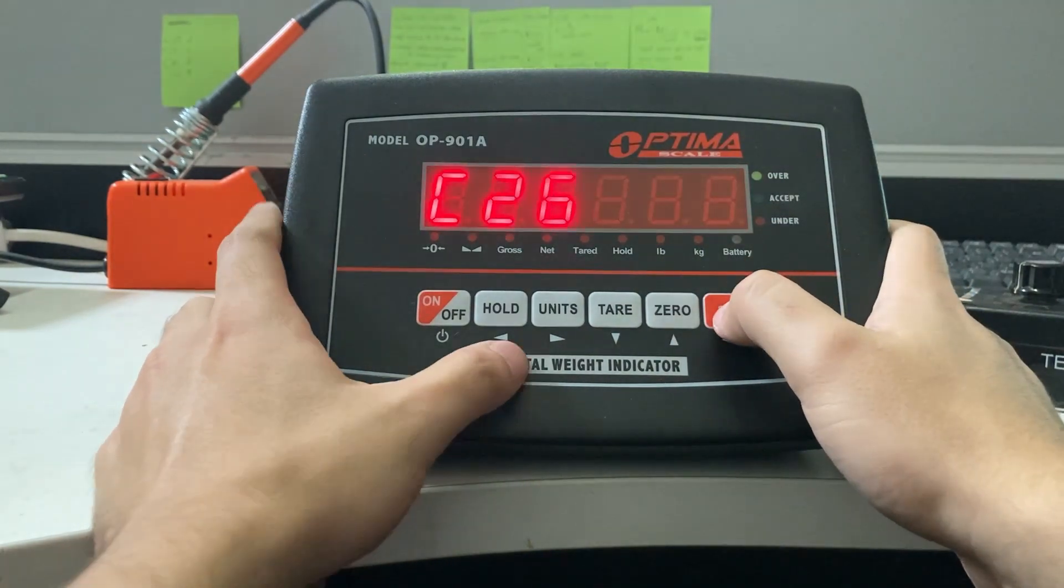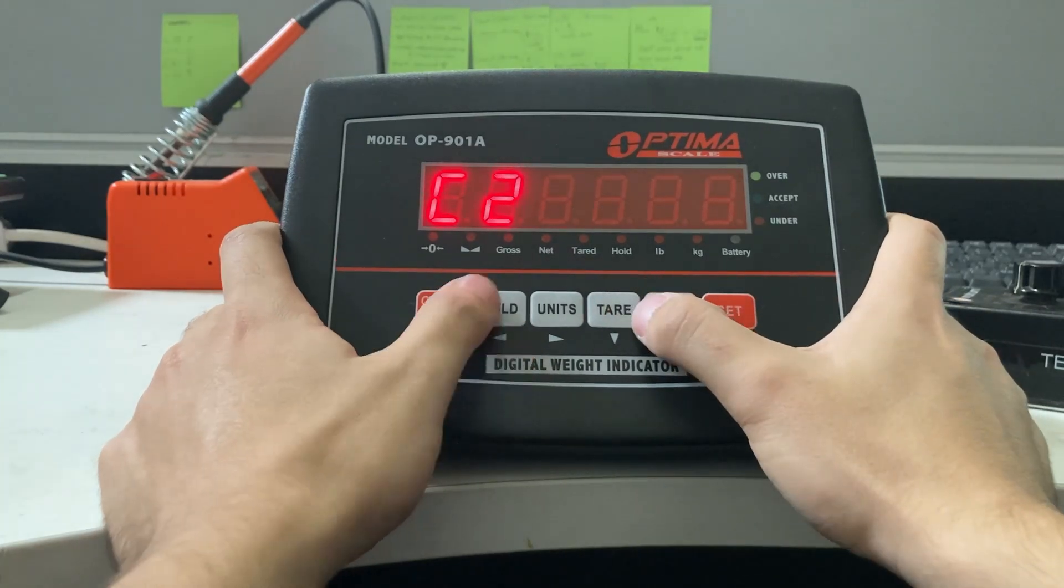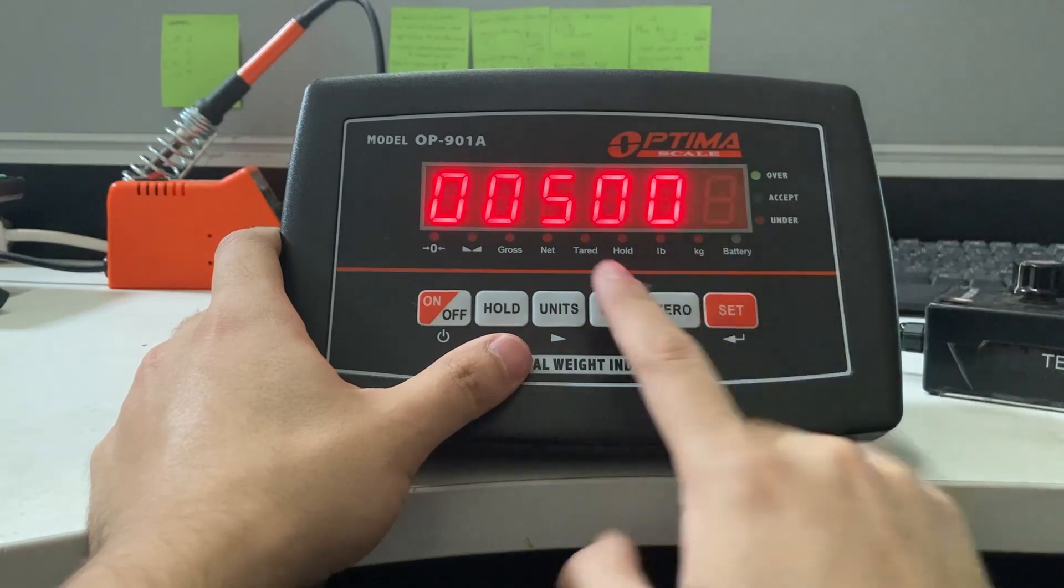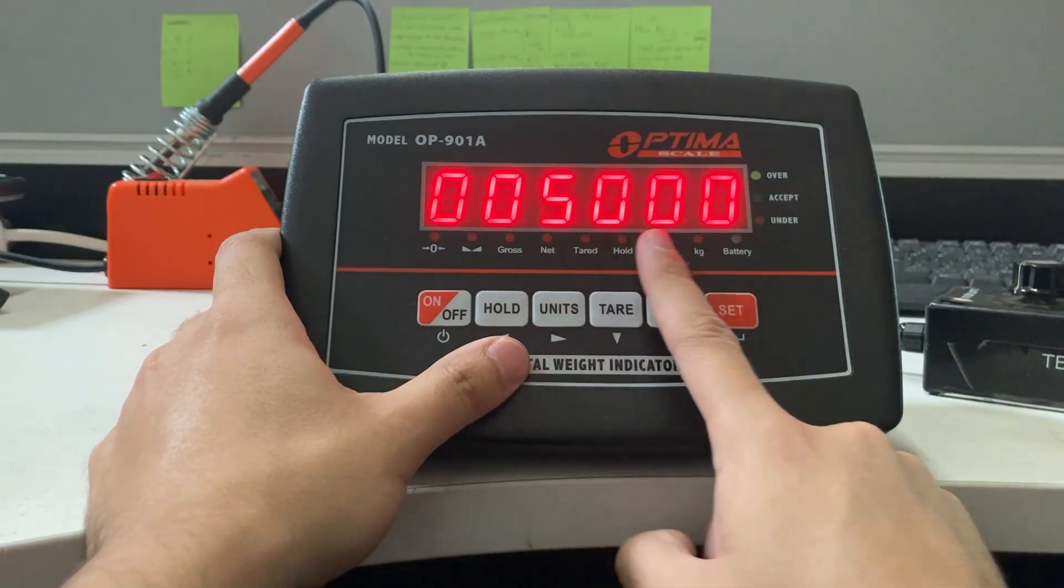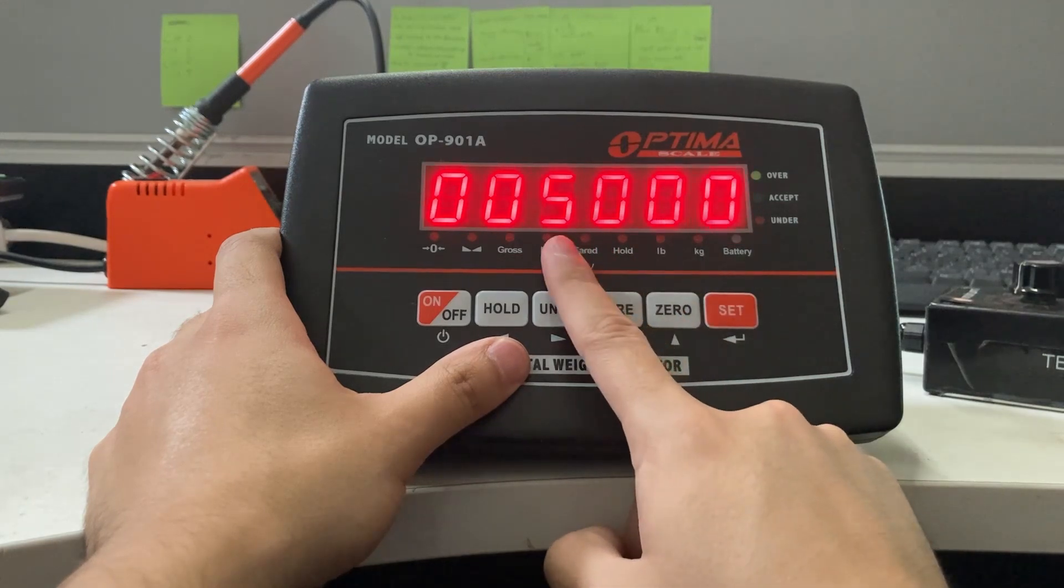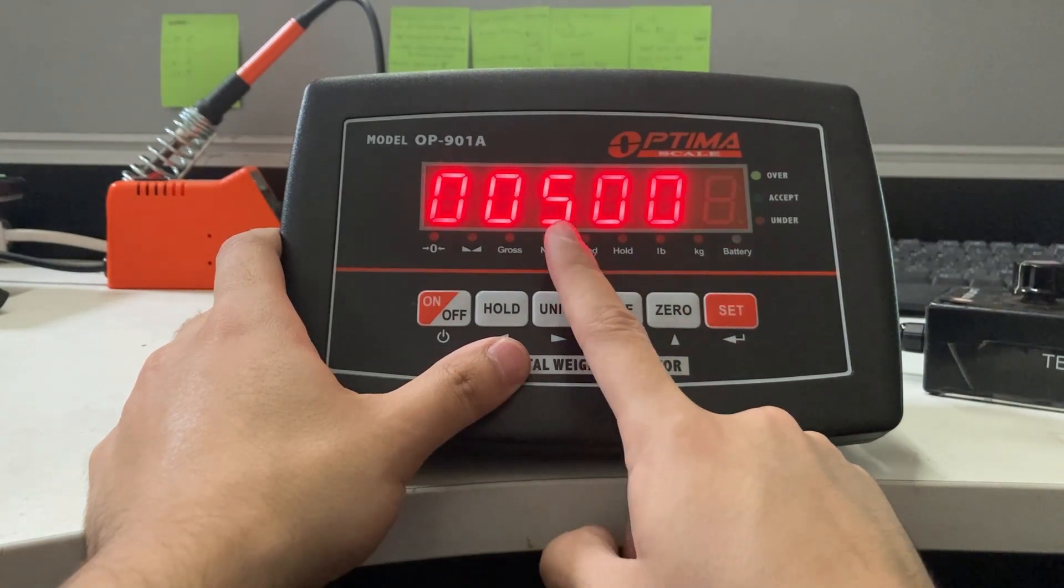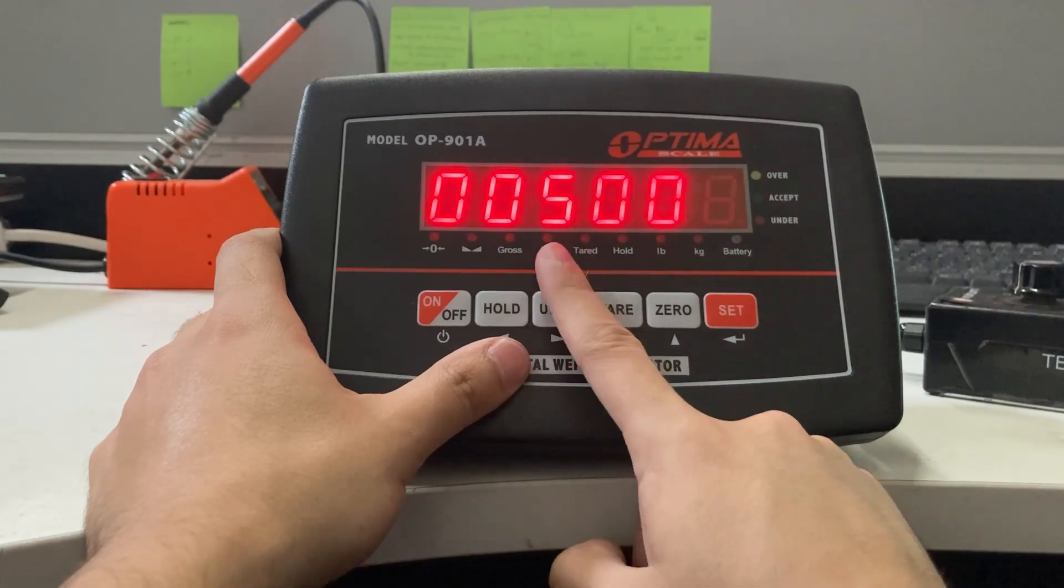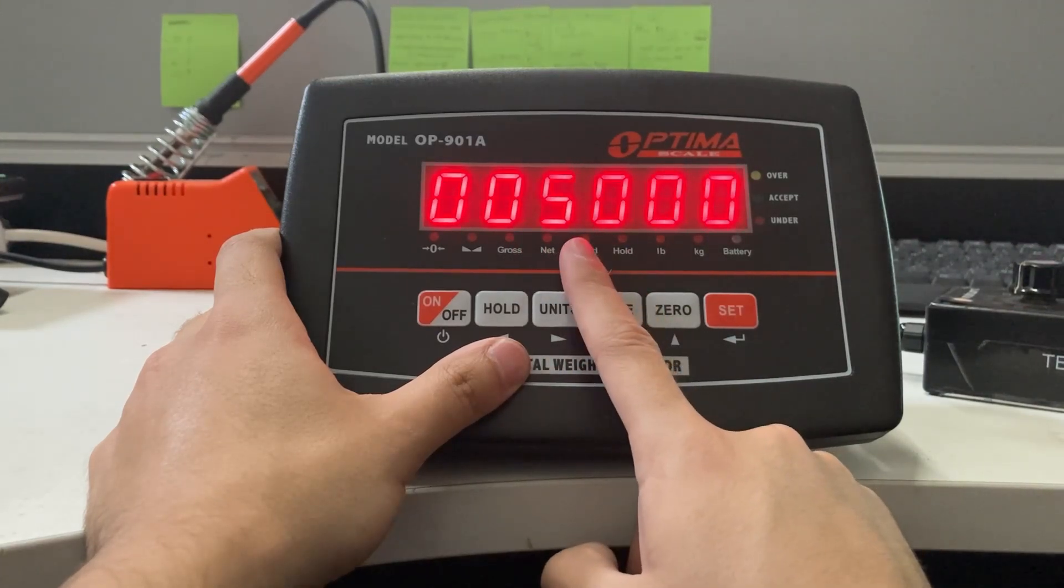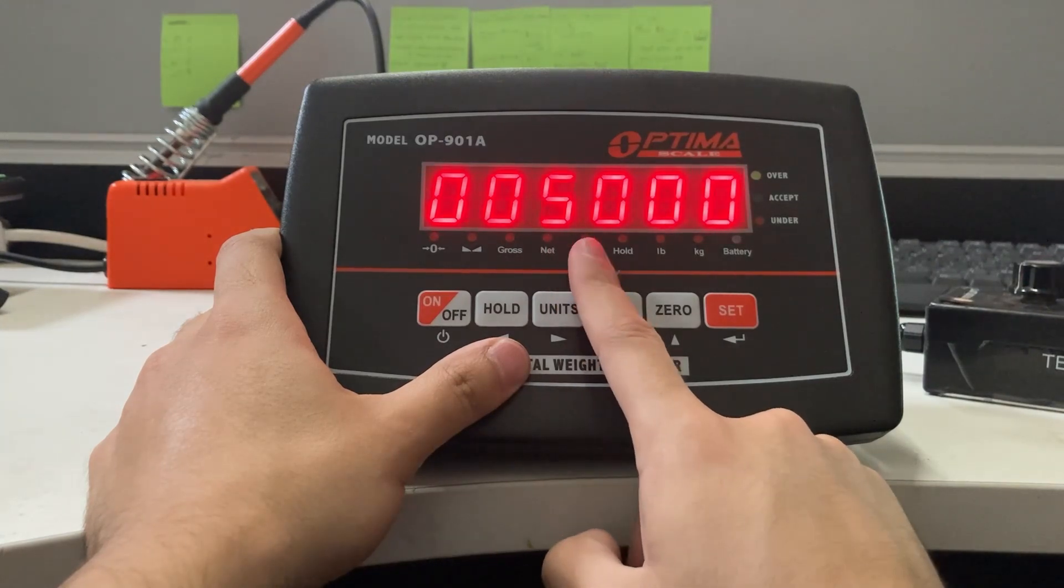You can always check your C04 setting. See, I currently have it at 5000, but you can always change your max capacity if you want. Right now at C25 100, I'm able to go positive 5000 to negative 5000. This will help prevent an underload or overload error that might occur if you go too far negative.